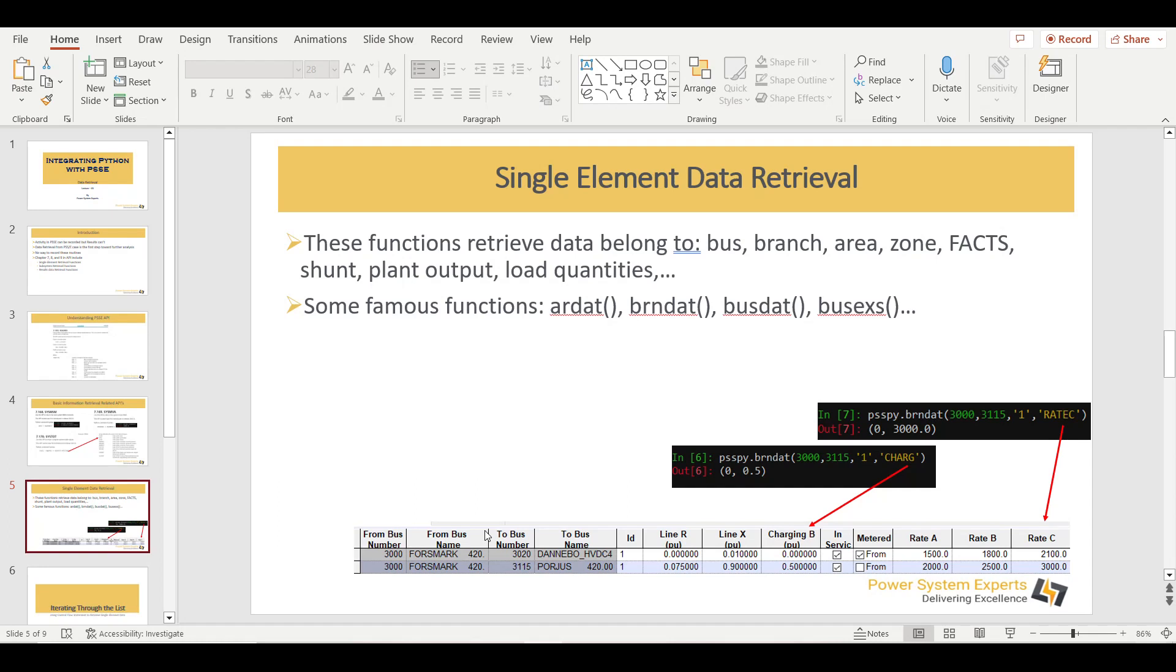To give you an idea, you see, this is the typical spreadsheet view of PSSE. You will see the data written in this particular form. So let's say you want to find the line charging. There is a function or an API within PSSE known as BRNDAT. So how you are going to implement it? You are going to write PSSPY.BRNDAT and then you are going to give the line details, the from bus, the to bus, the circuit ID. Once you have given this and then the argument, in this case, I want to see the line charging. So the argument for line charging or the keyword for line charging is CHARG. So when you pass this argument, you are going to get the line charging of that particular transmission line.